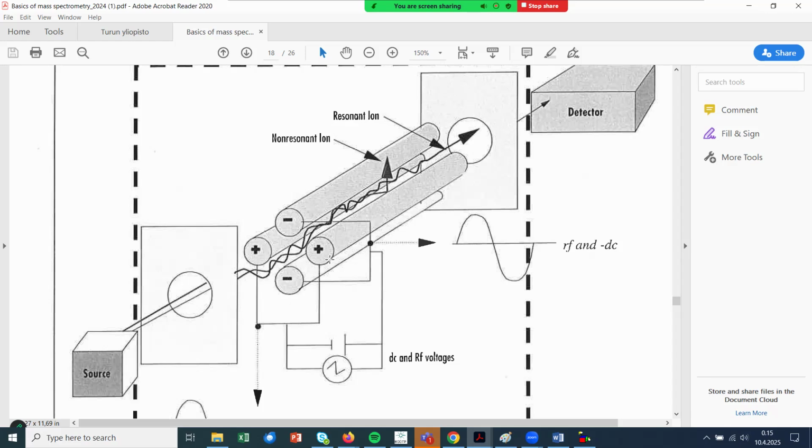So this is monitoring these individual ions. But what we often do, you remember the scan mode, is that we want to scan everything, for example, from mass 100 to 1000. So it means we need to switch the settings all the time. Let's say within 1 second, we can very easily scan the whole mass range from 100 to 1000.